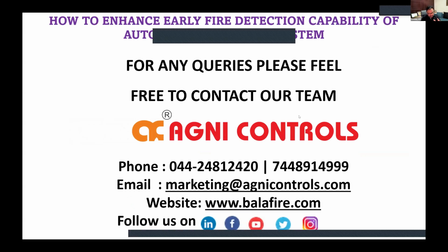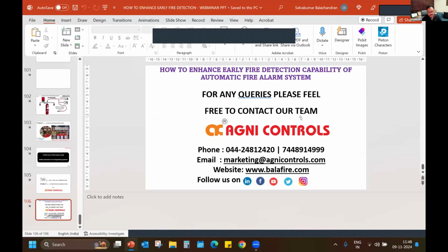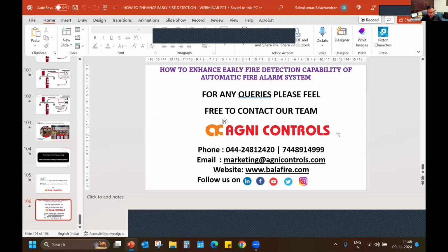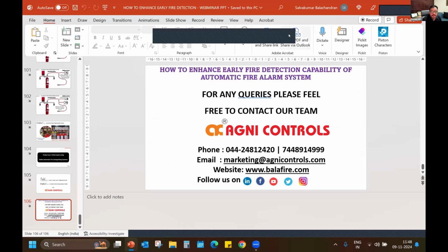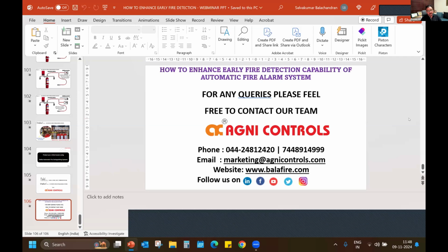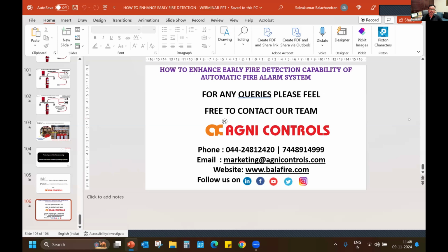It was quite a strong presentation. You touched upon the use of flame detectors, which is not generally specified by the consultant. When it comes to fire detection, it's just an optical smoke detector or multi-smoke detector. But there are a lot of questions on how you protect critical areas, including the car park area. The use of flame detectors, spark detectors and CO2 needs to be included in the design stage itself.